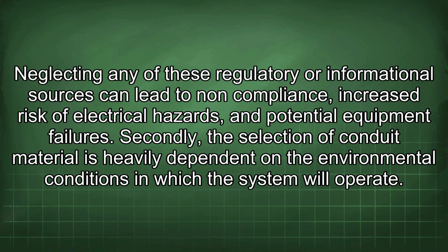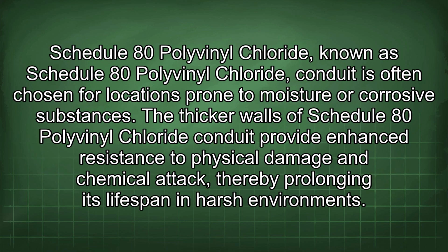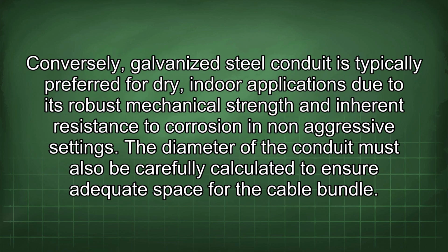failures. Secondly, the selection of conduit material is heavily dependent on the environmental conditions in which the system will operate. Schedule 80 polyvinyl chloride conduit is often chosen for locations prone to moisture or corrosive substances. The thicker walls of Schedule 80 polyvinyl chloride conduit provide enhanced resistance to physical damage and chemical attack, thereby prolonging its lifespan in harsh environments. Conversely, galvanized steel conduit is typically preferred for dry, indoor applications due to its robust mechanical strength and inherent resistance to corrosion in non-aggressive settings.